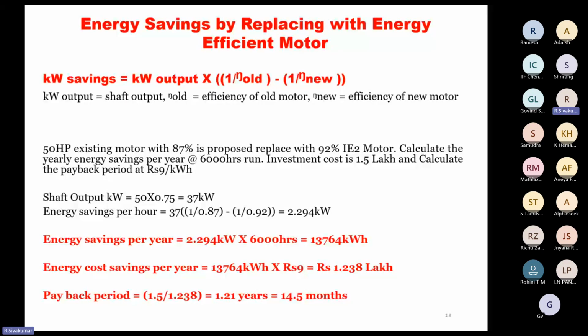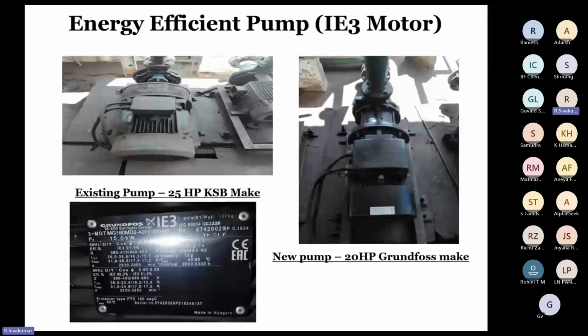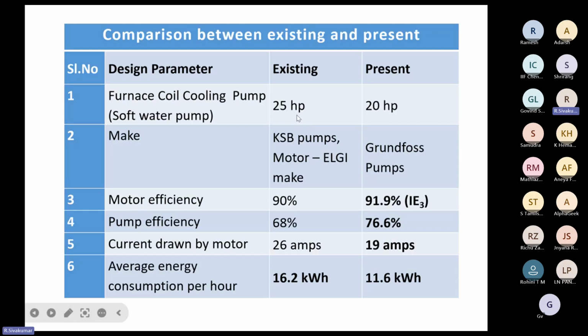This is one of the case studies implemented in Coimbatore, at one of the leading foundries. This is a coil cooling pump used in the furnace cooling system. The existing pump is replaced with an energy efficient Grundfos pump. The old pump is 25 HP. The new pump is 20 HP with more head and flow rate. The existing motor efficiency is 90%, the new pump's motor efficiency is 91.9%. Pump efficiency was 68%, the new pump is 76.6%.